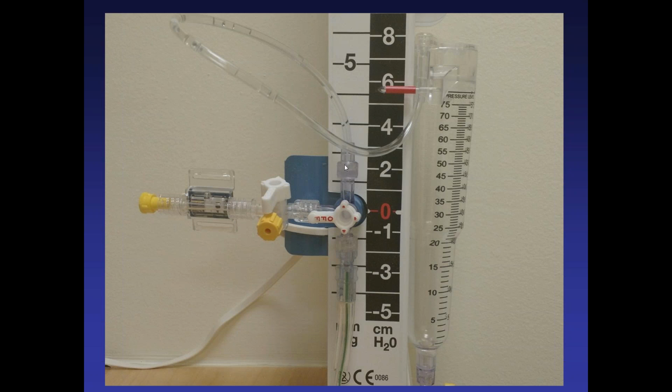All right, and then from here you see the CSF goes into this buretrol. And again, you can set the level of pop-off levels, so to speak, at which you want CSF to come out of the patient. Any questions about this collection setup? This is manufactured by Integra. That's what it seems like the majority of places use. That's what we use here.